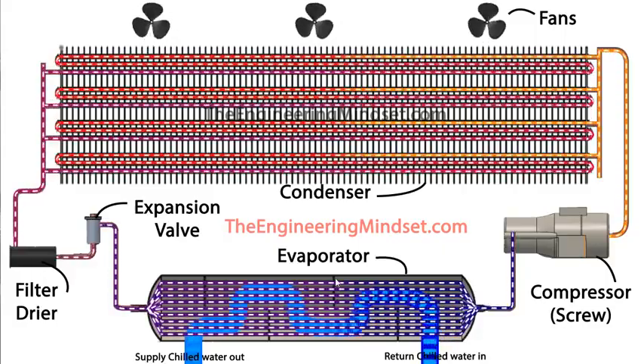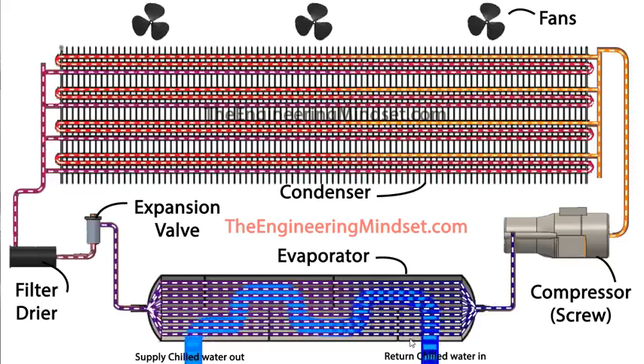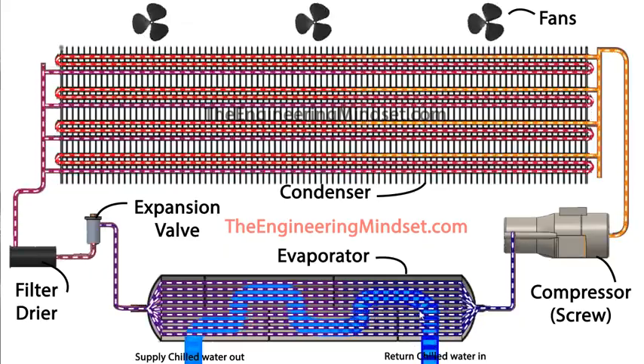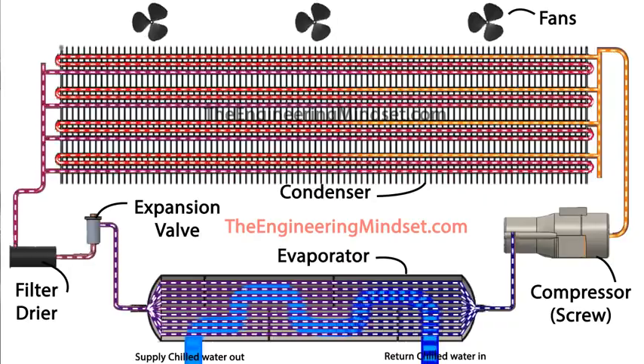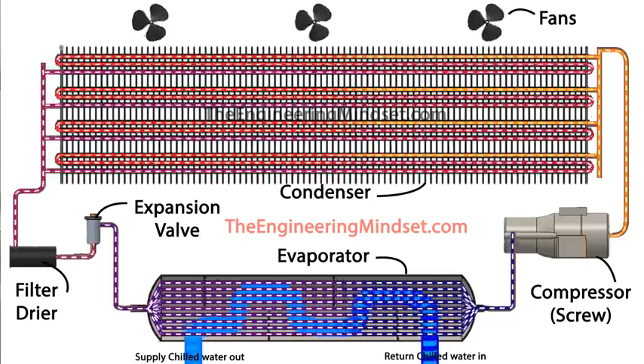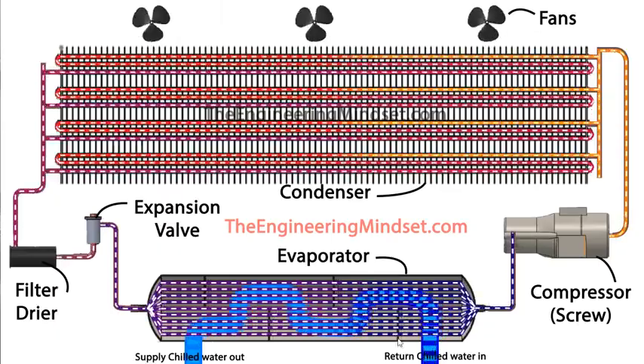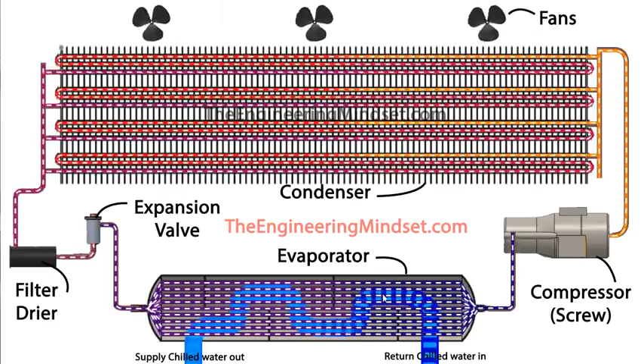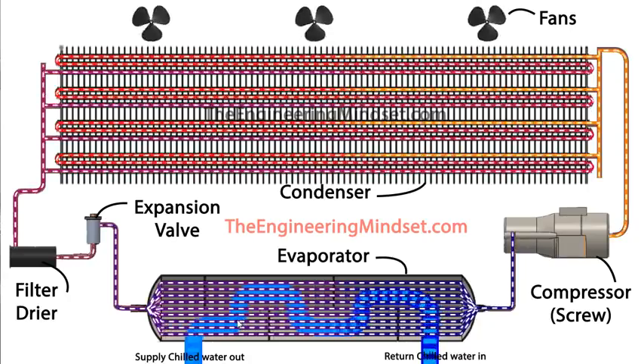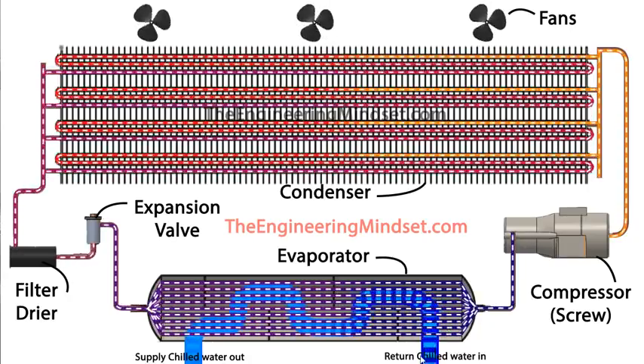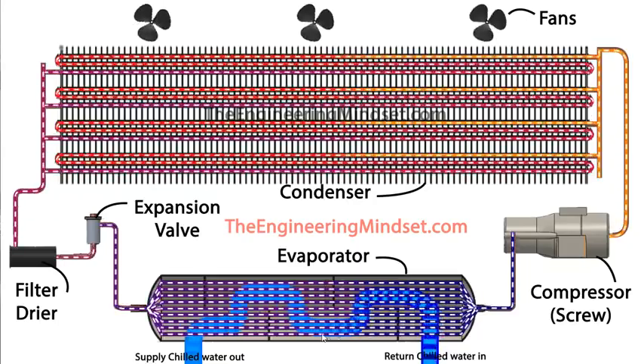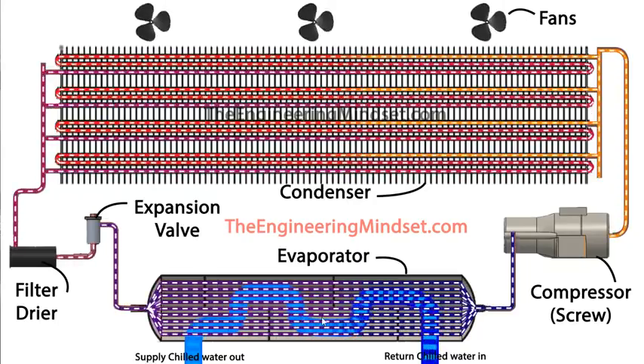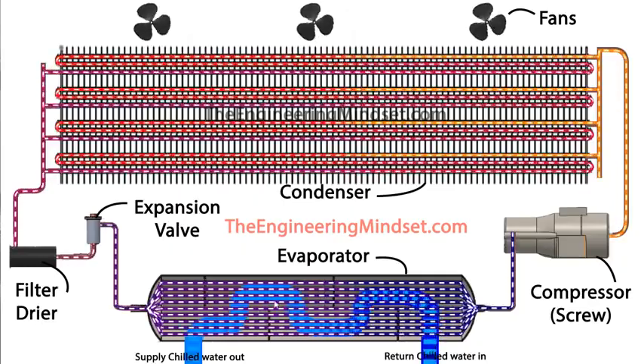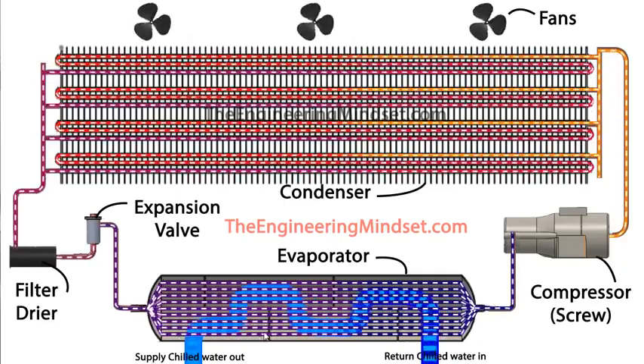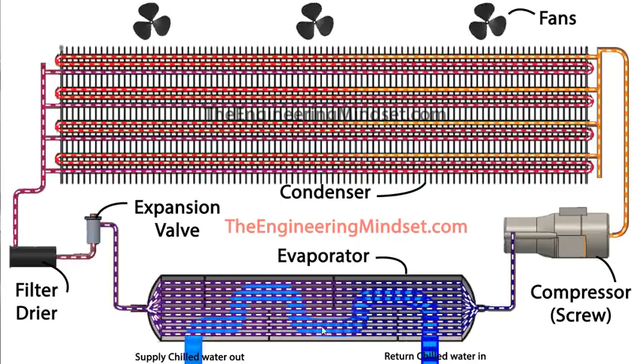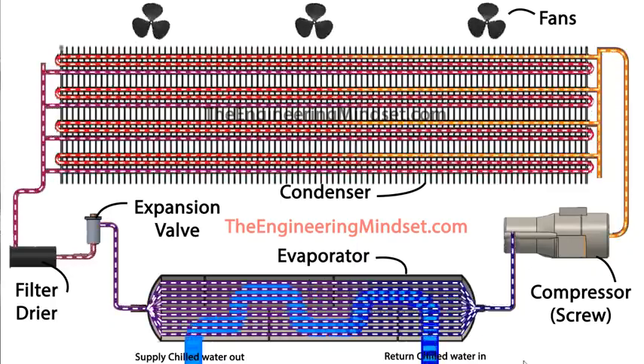Also notice that there are some restrictions within the heat exchanger. These are known as baffles, and what happens is the chilled water enters here and you'll get much greater heat transfer if the flow of water is turbulent. So you add these baffles in, and that will cause the water to change direction sharply. In the animation it's a bit smooth here, but this would really be very turbulent in there, passing through and colliding and moving across the surface of these tubes and taking more and more of that thermal energy away, so that it leaves as a very cool liquid ready to go around the building again.